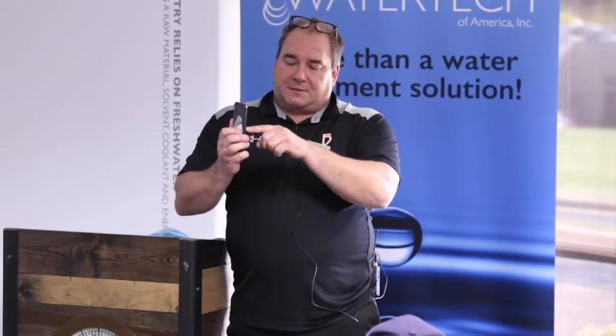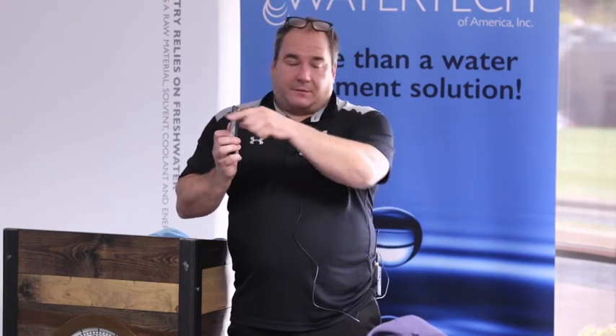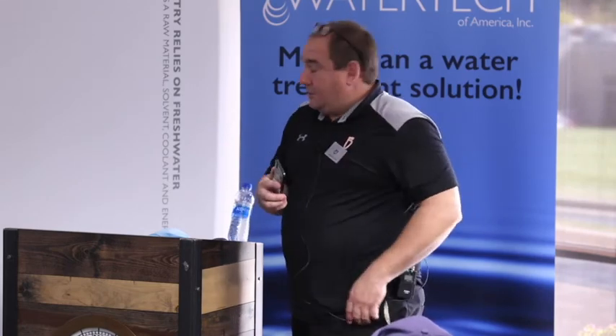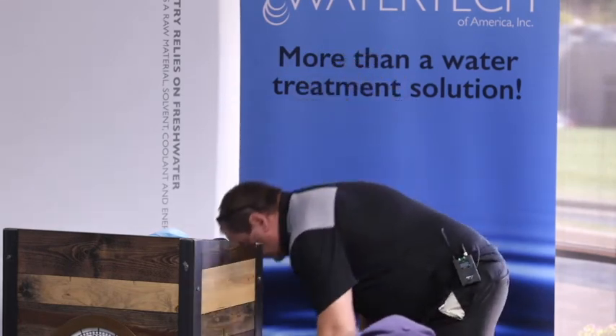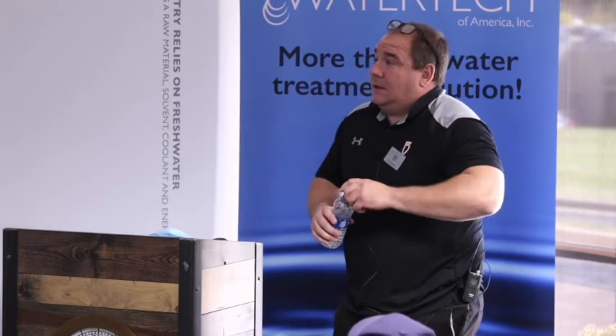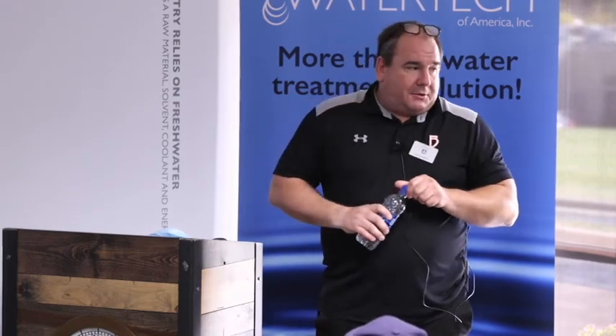Instead of it coming right to the surface of whatever it's in, wherever we're injecting the chemistry, the idea is that it puts it in further so that it doesn't react with anything immediately. It helps prevent some immediate reactions that might happen if you just put it at the surface and let it react. So it puts it further into the water, which helps with reactions and mixing. So I would say, yeah, it probably should. And this injection quill can come in different lengths. It's a great question, though, but yeah, probably should.